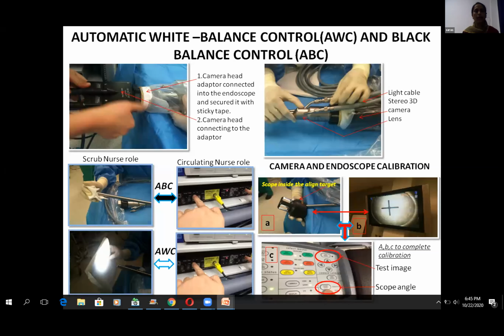Same thing, the AWC is white balancing. Here, use the white paper to do the white balancing. And for the camera, there are 2 degrees we are using for the endoscope, 0 and 30. In the calibration mode, we have to adjust, we have to do the 2 separately, 0 and 30, with the scope alignment.